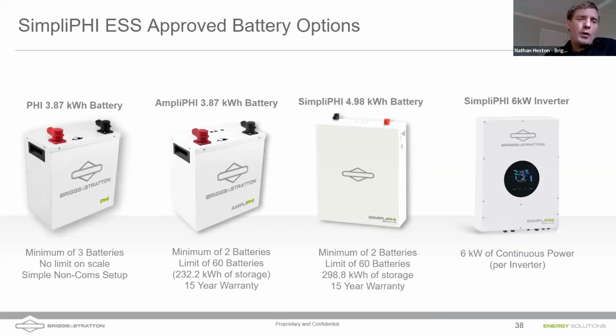The batteries that we offer come in 24 and 48 volts. The PHI battery is one that we've really got a lot of history with and is typically used in off-grid markets. That does come in a 24 volt option, and it comes in a 48 volt option as well. The communicating batteries that you're looking at, the AmpliPHI and the wall hung outdoor rated SimpliPHI 4.98, only come in 48 volt nominal sizes. So it's important to consider that.